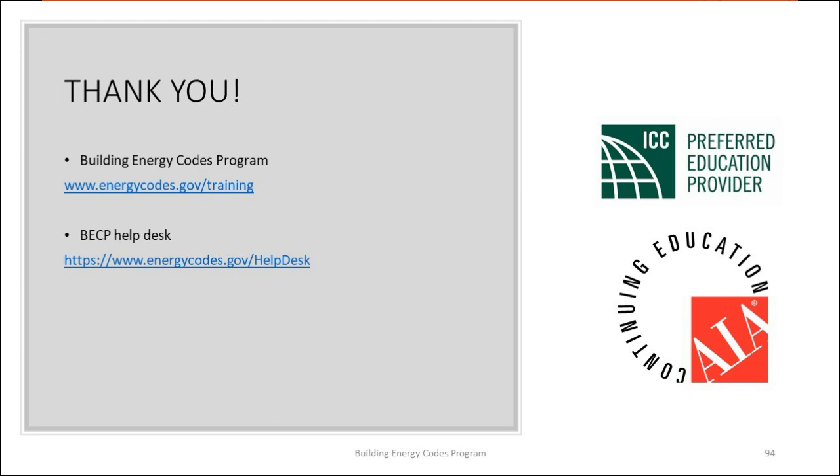There's another question about the building area method and the space by space method. Can you mix those two in your proposed and baseline building? And the answer is no. In general, you have to use the space by space method in both cases unless you don't know what the spaces are going to be in your proposed building, because it's a future build out like a tenant improvement. In that case, use the building area method, and you have to use that in the baseline as well.